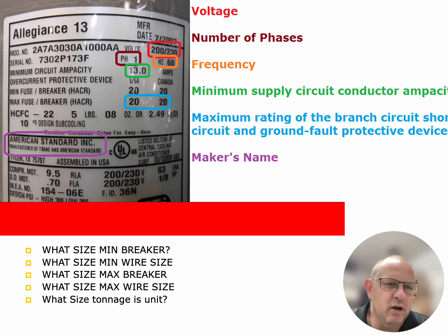So we'll continue to look at our nomenclature plates or our tags on our outdoor units. This one is an Allegiance 13, manufactured in 2007. There's a couple of questions that I need to ask myself for this particular unit. What size minimum breaker can I put on it? What size minimum wire size can I put to that breaker? What size maximum breaker? So what we're doing here is we are combining both what you have learned in electrical and what you have learned in air conditioning, and we're putting them together so that when we go out and look at these particular units, we will have an idea about what breaker size we have to put on this unit based on the nameplate of that unit.